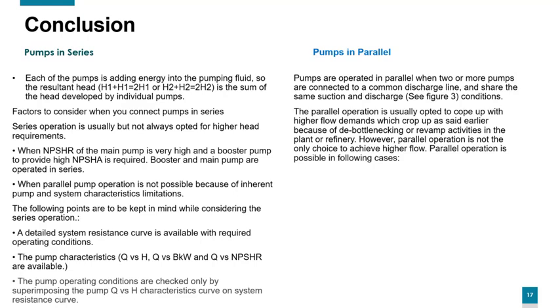Second, pumps in parallel. Pumps are operated in parallel when two or more pumps are connected to a common discharge line and share the same suction and discharge. The parallel operation is usually opted to cope up with higher flow demands, which crop up, as said earlier, because of debottlenecking or revamp activities in the plant or refinery. However, parallel operation is not the only choice to achieve higher flow.